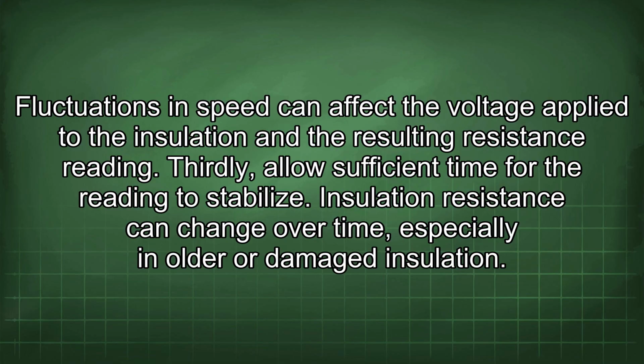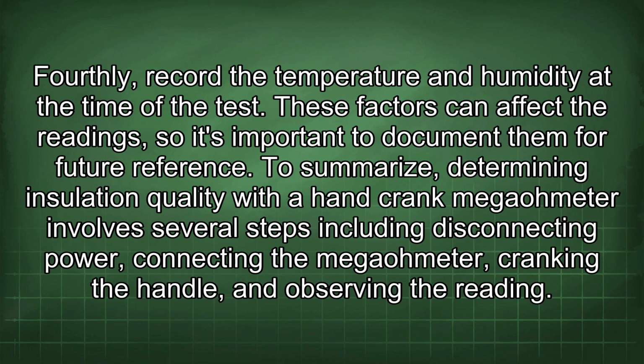Thirdly, allow sufficient time for the reading to stabilize. Insulation resistance can change over time, especially in older or damaged insulation. Fourthly, record the temperature and humidity at the time of the test. These factors can affect the readings, so it's important to document them for future reference.